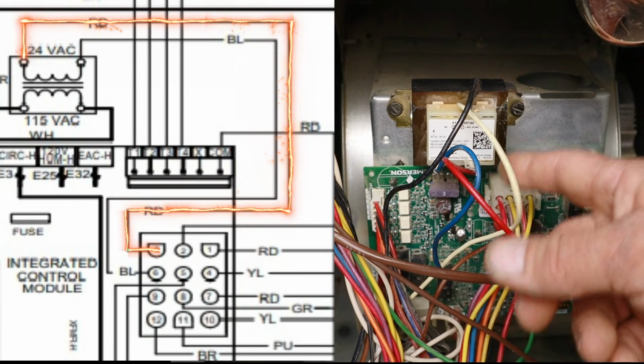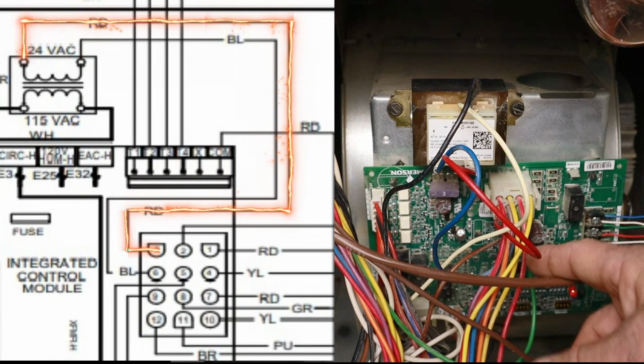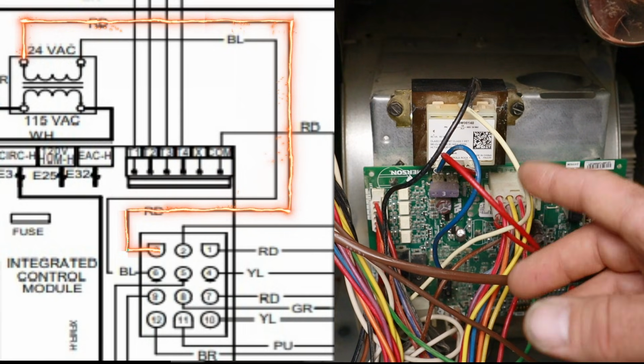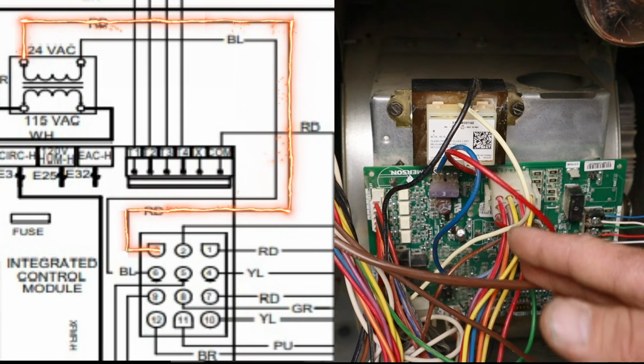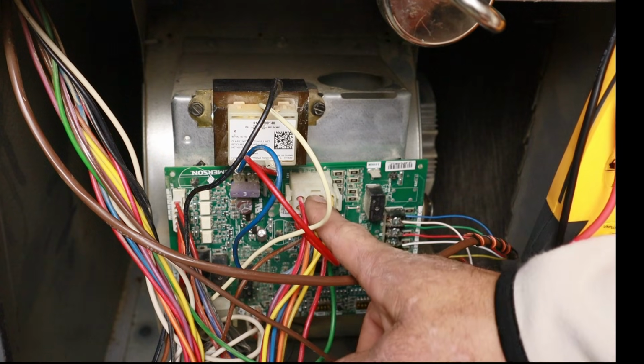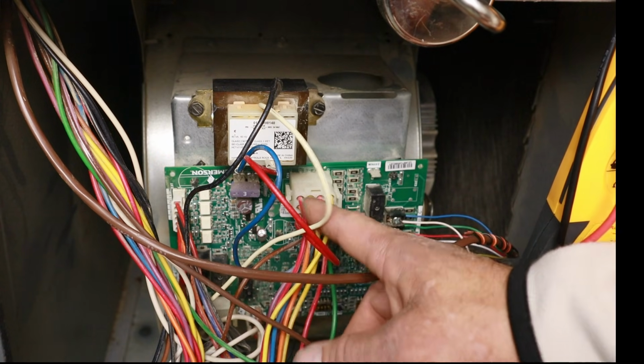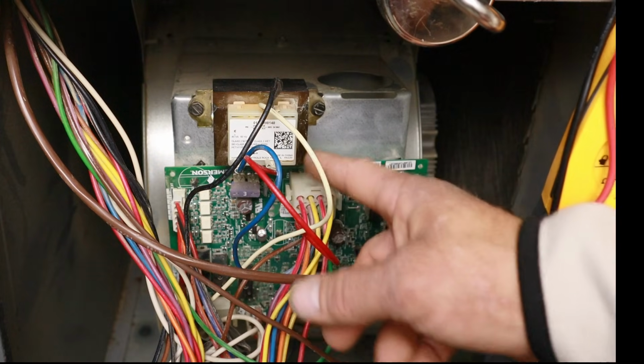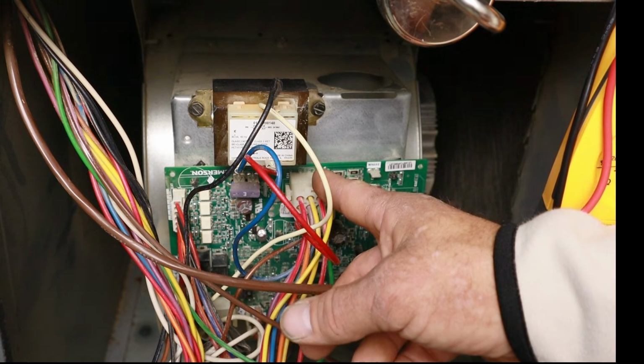It's going to come out at 24 and go back to our control board. So regardless of how it's wired, you're usually going to see that in all furnaces. Now the next step here, if we were doing diagnostics, is to make sure the 24 volts is actually making it to the control board.